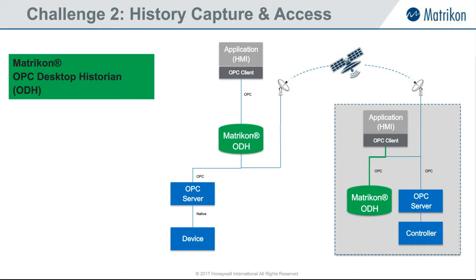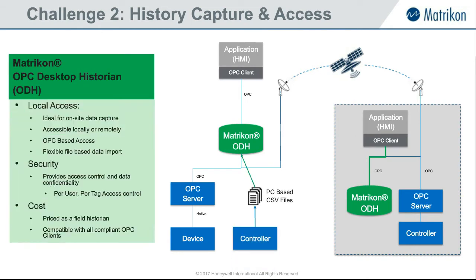And not only would you be able to pull that in through an OPC source, but we realize that sometimes you'll have devices that will basically spit out files or update files. So there are different strategies that they use, and they would basically write that to some location in the network. Typically on a PC, they'd be storing it in a particular directory or multiple directories. And basically, as the file gets updated, it changes its timestamp or its size changes, and that's how you can detect that additional information has been added from a device.